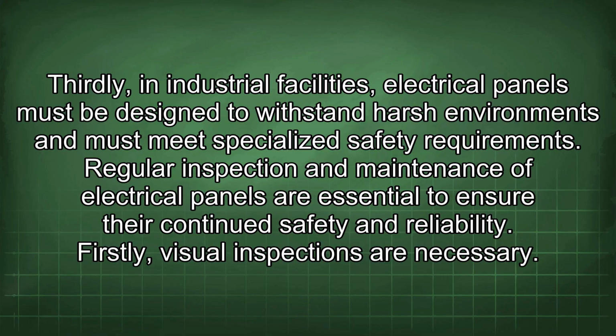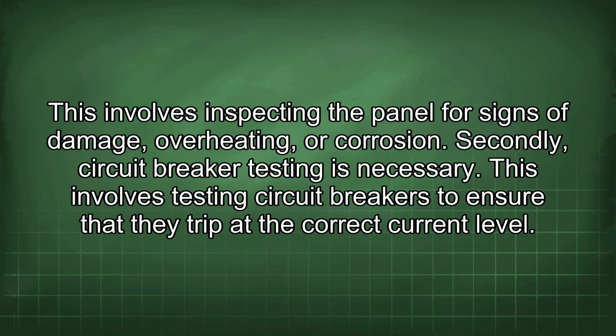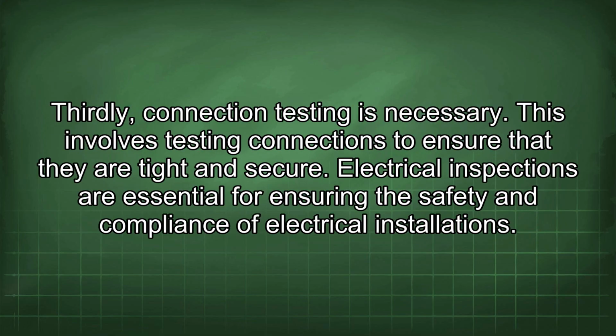Regular inspection and maintenance of electrical panels are essential to ensure their continued safety and reliability. Firstly, visual inspections are necessary. This involves inspecting the panel for signs of damage, overheating, or corrosion. Secondly, circuit breaker testing is necessary. This involves testing circuit breakers to ensure that they trip at the correct current level. Thirdly, connection testing is necessary. This involves testing connections to ensure that they are tight and secure.